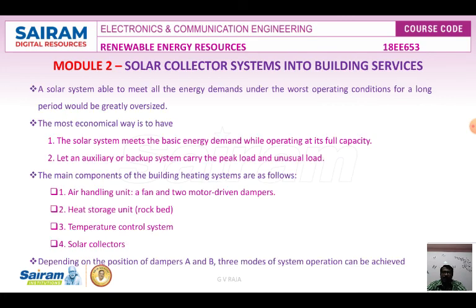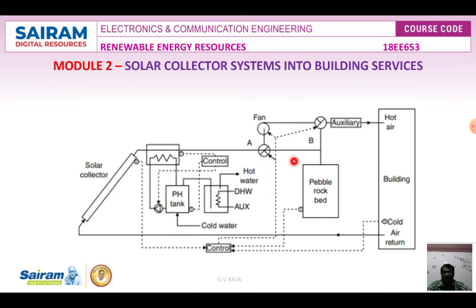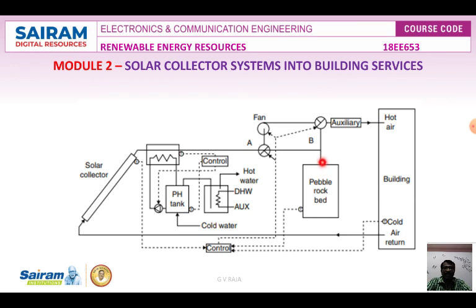In the third mode — damper A is closed, damper B is open — this mode operates during cloudy or night times. The return air from the building, which is cold, is pulled through the rock bed, where it is heated. That heated air is picked up and circulated back. If the temperature is insufficient, the auxiliary furnace activates automatically, the fan rotates, and hot air is blown into the building.